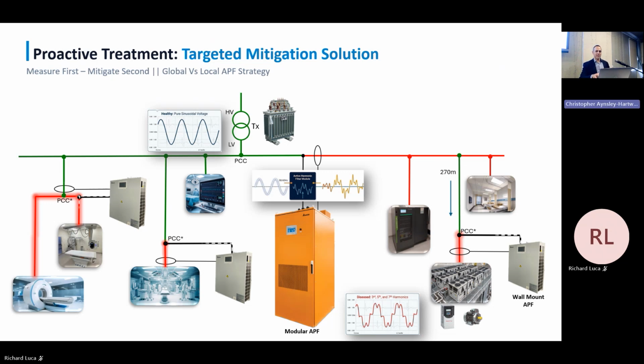But what happens is deep within the network, on the right-hand side, you've got your HVAC plant. We've got harmonic distortion, which is propagating throughout the network. And you may have a large run of cable, 270 meters, to this HVAC plant. So local compensation makes sense for that because it will save all that distorted energy from flowing in that particular site. The same thing with all your sensitive medical equipment. With local compensation, we're effectively trapping the harmonics locally from propagating throughout the entire network.